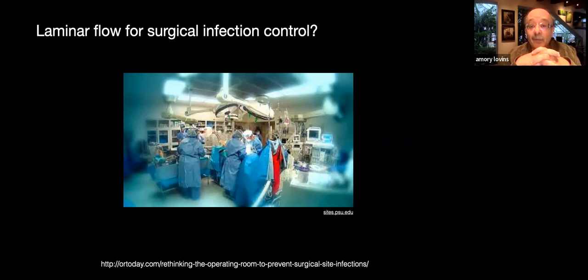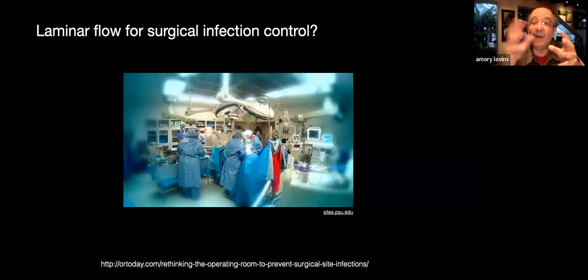Of course, operating theaters need laminar flow using cleanroom technology. Don't they already do that? Well, surgeons and hospital engineers tell me it's common only for orthopedic and other implant operating rooms where infection risk is especially high, but not generally in many others. You see, operating rooms lack the airborne contaminant control standards used in clean rooms, and many ORs have ceiling obstructions that add turbulence. Meanwhile, the Centers for Disease Control and Prevention keep raising their guidelines for air changes per hour in the room, and that breaks hospital space constraints and financial budgets.